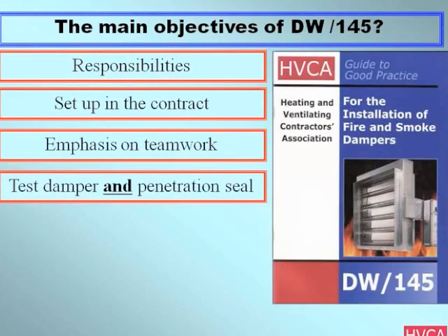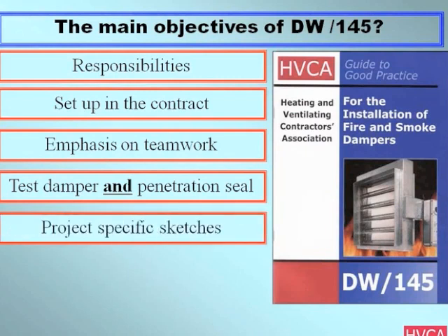One of the main objectives of DW145 is that the damper must be tested along with the penetration seal. In the past, dampers have been tested for fire penetration and so on, but the penetration seal is just as important, because it's not always the case that fire is passing along the ductwork - it can also be affected outside the ductwork via the penetration seal.